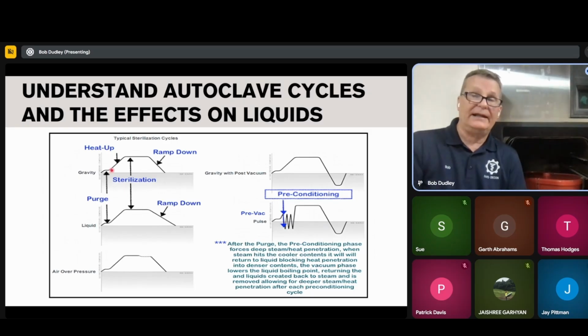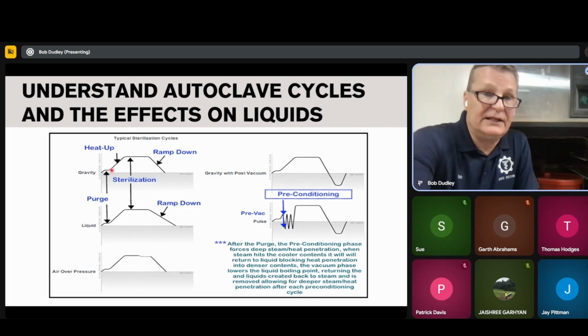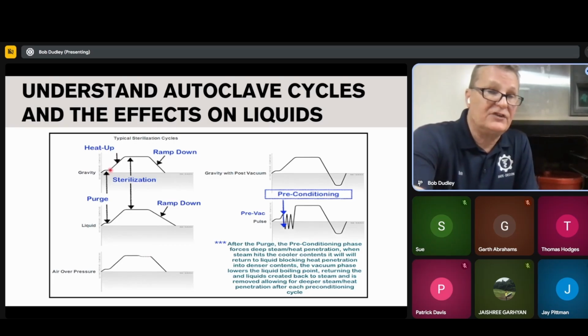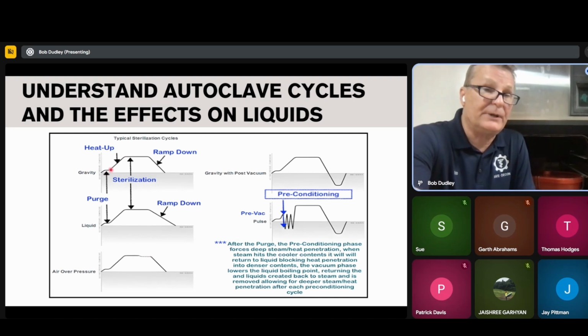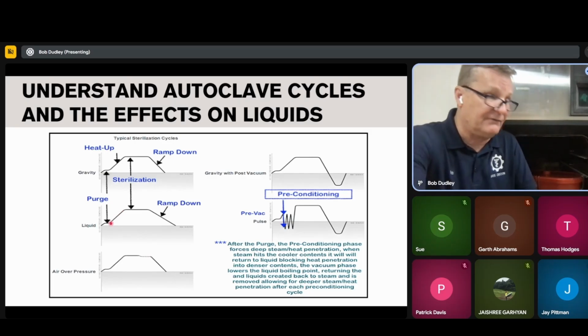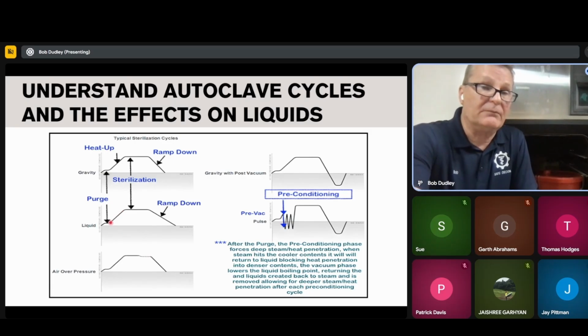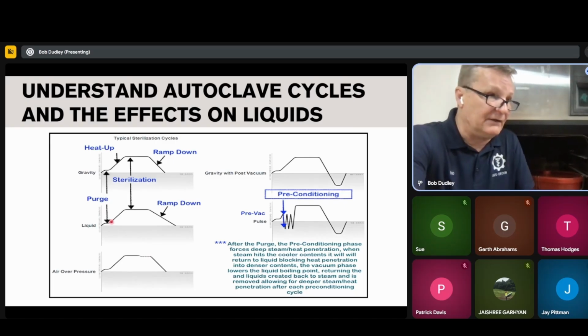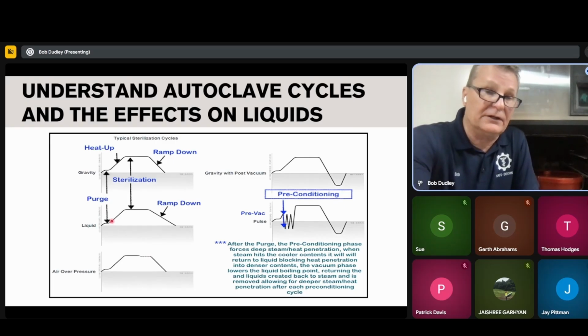When you understand how the effects of steam, mist, and what goes on in this autoclave, I'll detail that in the tests and explain why failures happen. But here it has to go up kind of slowly because you're not getting the steam penetration to the middle. And it's the same thing with liquids. Liquids here, they have to ramp up kind of slowly because the liquids have this insulating factor to them. So depending on if you're doing 100 milliliters or you're doing 5 liters, it takes a while to heat up.